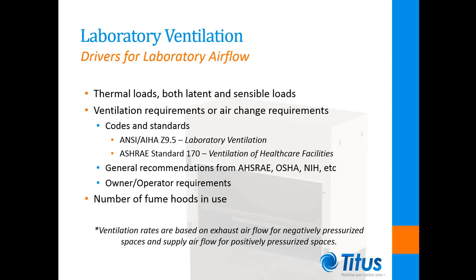In labs with negative pressurization requirements, ventilation rate is based on the exhaust airflow, which is used to minimize the buildup of odor and contaminants not captured at the source. In labs with positive pressurization, supply airflow establishes the ventilation rate, as it is used to dilute the lab with clean air to achieve the desired level of air cleanliness.